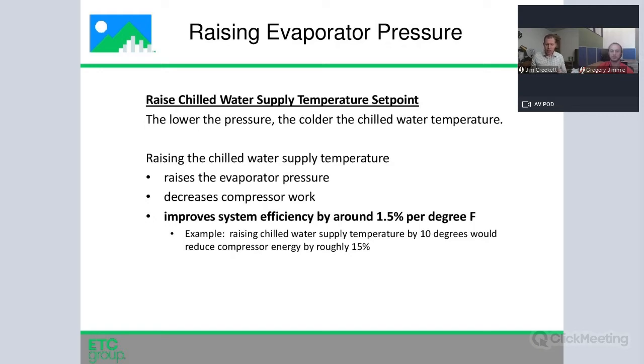And each degree Fahrenheit that you raise on an air-cooled chiller translates into about 1.5% energy savings. So if you were able somehow to go from 42 degrees Fahrenheit of chilled water supply to 52, you could expect around 14 or 15% energy savings at the compressor. So that's the first way to do it, but it's not the only way.